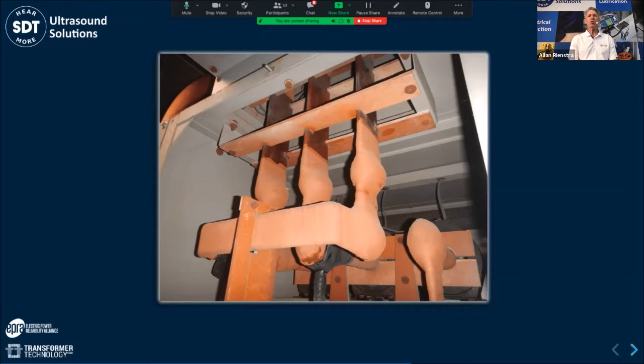What you're looking at here is again just a three-phase transformer. What Craig was able to pick up was partial discharge activity, not at this one, but at this one - you can see a bit of white nitrous building up around there. There was no heat signature from this. He opened it up and looked at it with his infrared camera and saw nothing, but clear as a bell he heard partial discharge in the ultrasonic range.